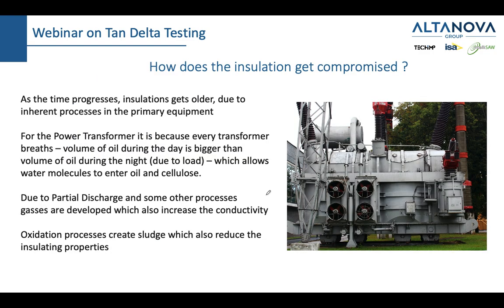But how does the insulation actually get compromised? Well, what happens is that the insulation gets older. It gets old. All of us, we get old, and all of us, including the transformers, breathe. We said before that the transformer breathes. So for those of you who know, just bear with me. And for those of you who don't know, imagine a situation of a 250 MVA transformer, which is a big transmission transformer, which is supplying a city of 100,000 people. During the day, the temperature outside is 30 degrees Celsius or 25 degrees Celsius. And the transformer is being used to power air conditioners and people's lives. People are awake during the day. The transformer is maybe used at 70 or 80% of nominal power.